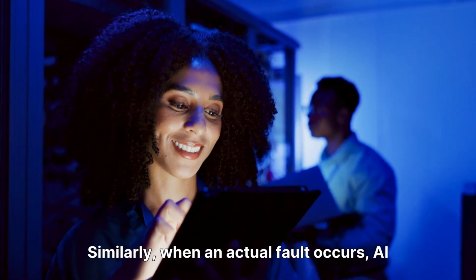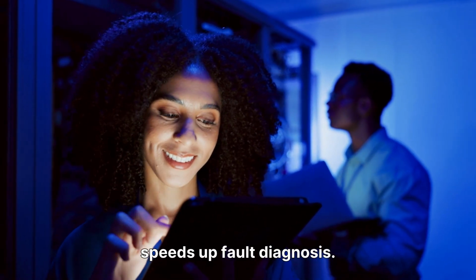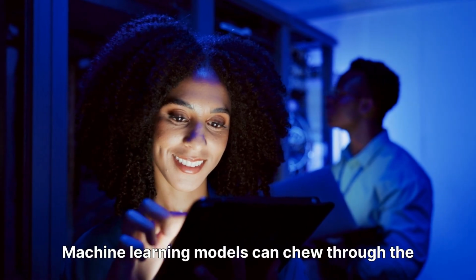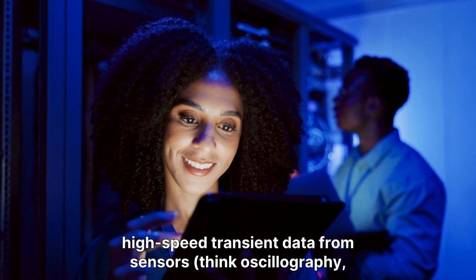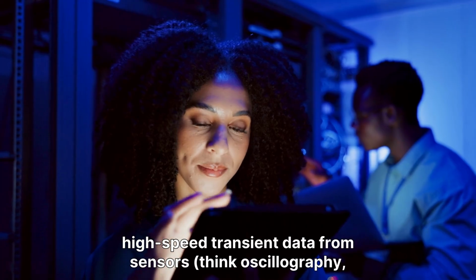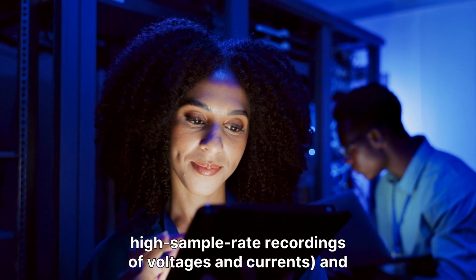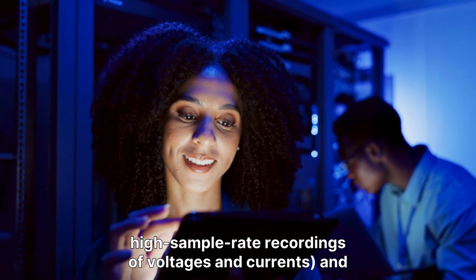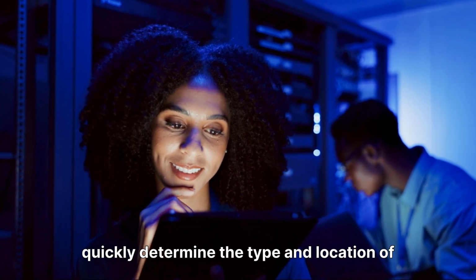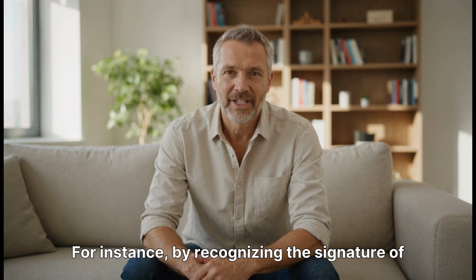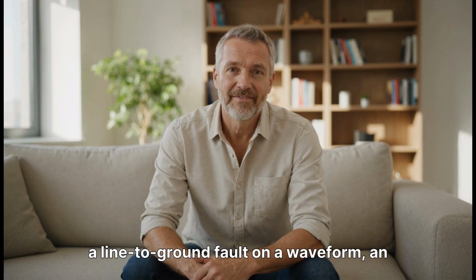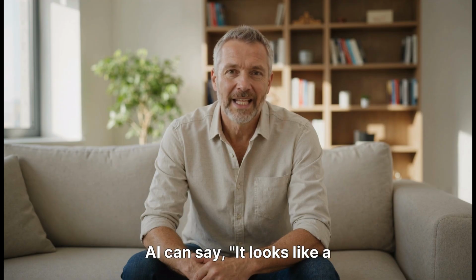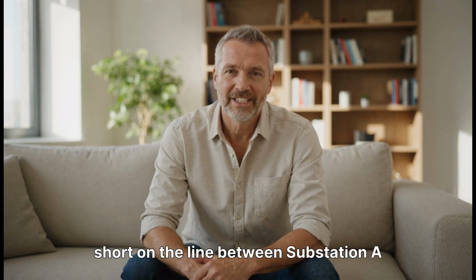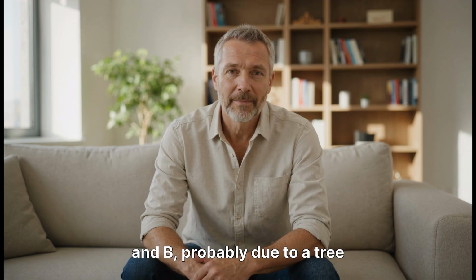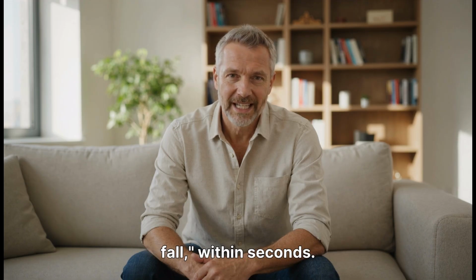Similarly, when an actual fault occurs, AI speeds up fault diagnosis. Machine learning models can chew through the high-speed transient data from sensors, think oscillography, high sample rate recordings of voltages and currents, and quickly determine the type and location of a fault. For instance, by recognizing the signature of a line-to-ground fault on a waveform, an AI can say it looks like a short on the line between substation A and B, probably due to a tree fall, within seconds.